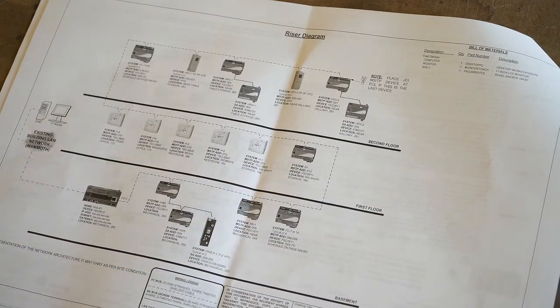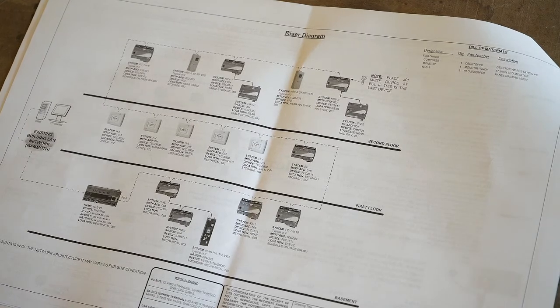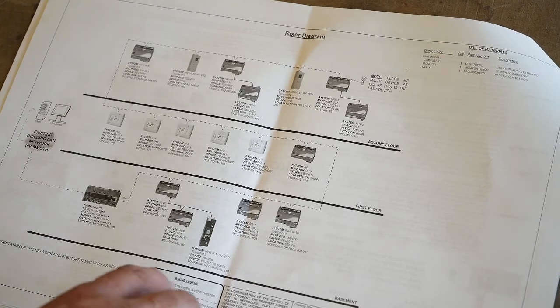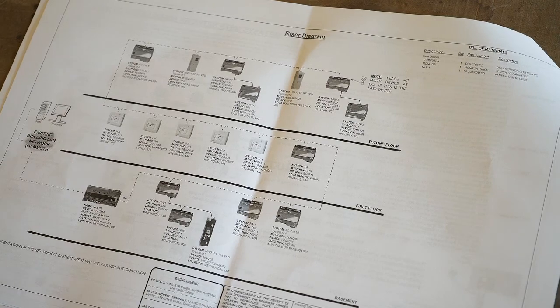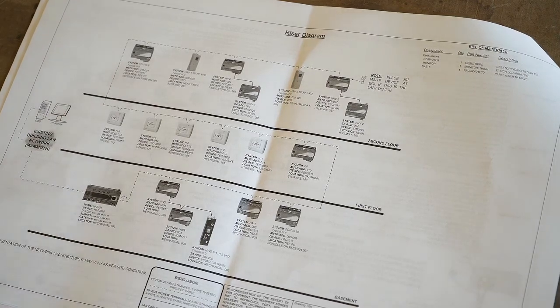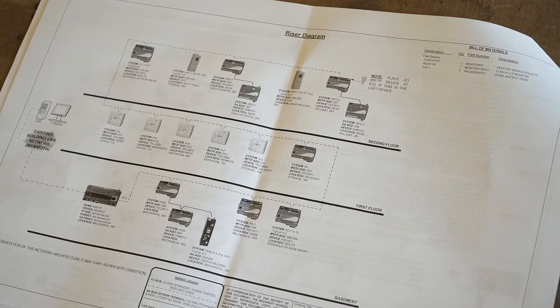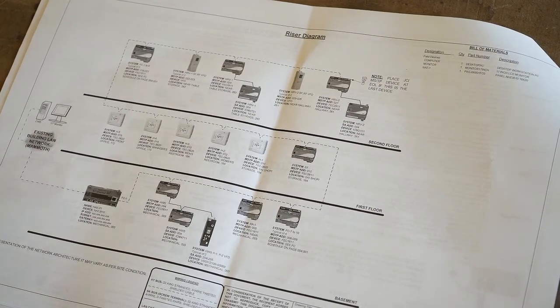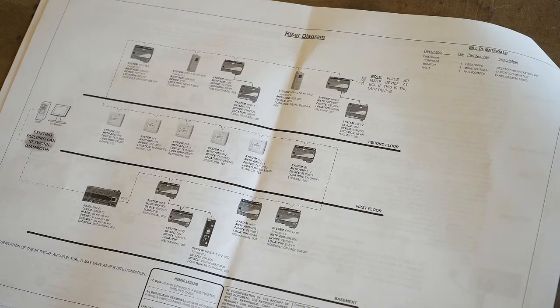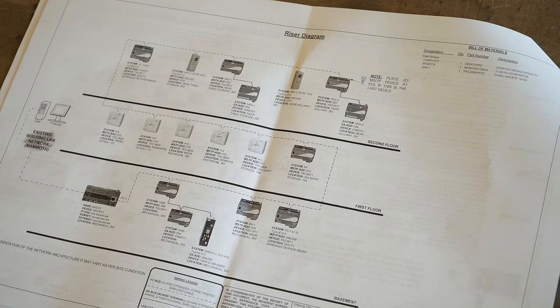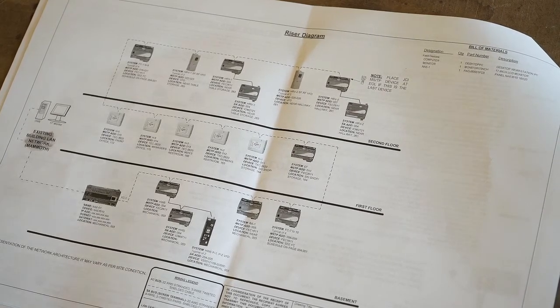Are you doing a reset schedule on any of these hydronic systems? We're doing a reset schedule on the water coming out of the steam heat exchangers. Okay. We'll get into that when we get downstairs so we can actually point to it and go through it. But coming out of the steam heat exchanger, we're doing a reset schedule basically just on the hot water supply going to the building, which... Just with a three-way bypass or something? Yeah, we'll look at it downstairs, but we've got two-stage steam valves and stuff like that on it. So we'll go through that after a bit.